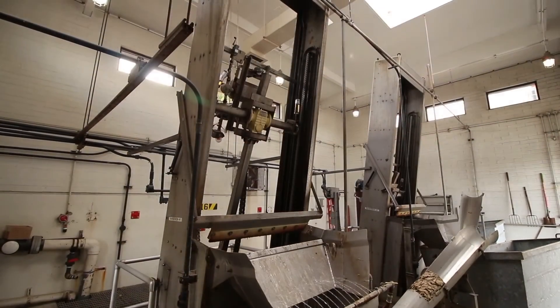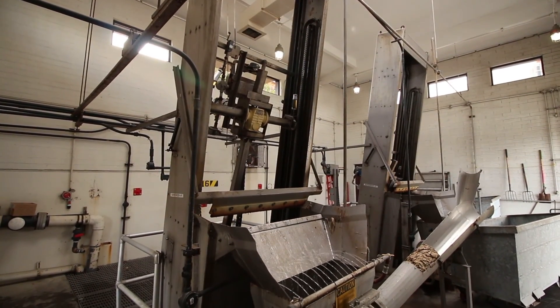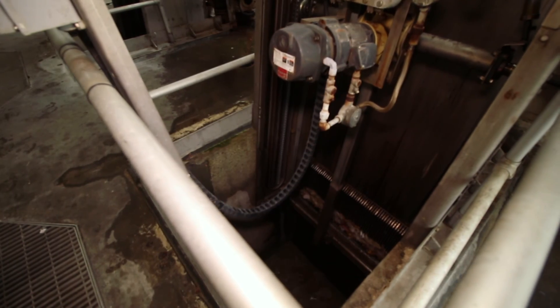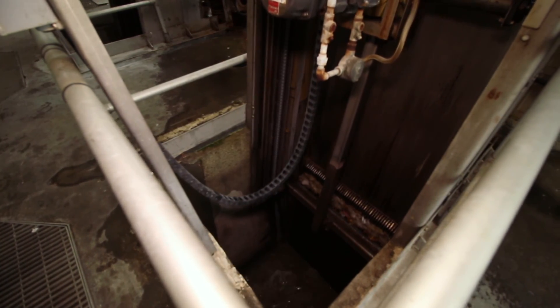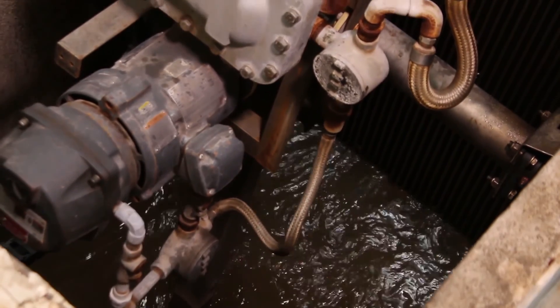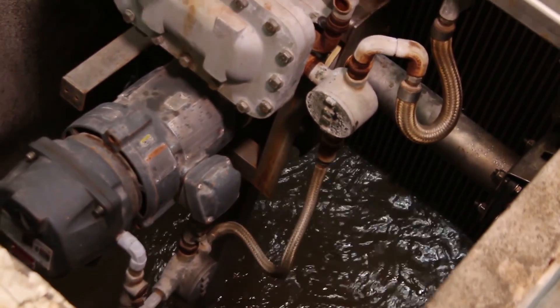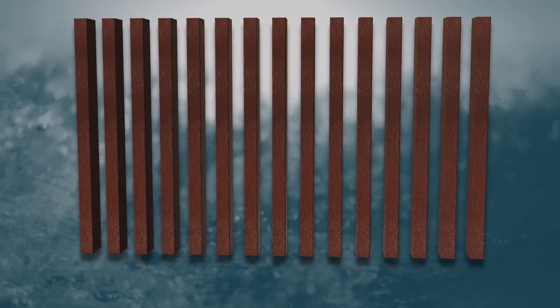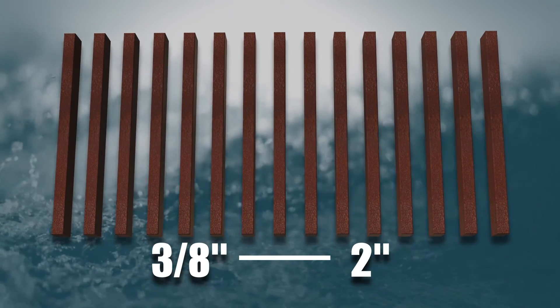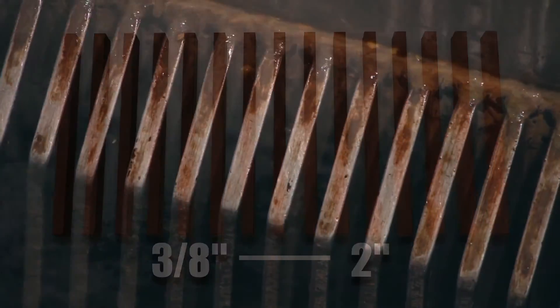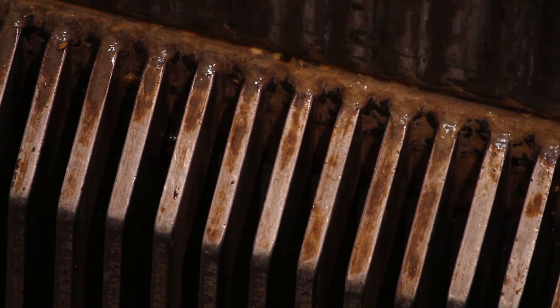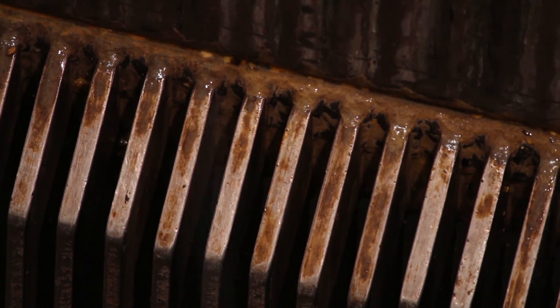This facility has two mechanical bar screens running in parallel. Each screen is mounted in a channel where wastewater or sewage flows through. The screen traps solid material such as rags or rocks. Bar screens are designed with evenly spaced parallel bars from three-eighths to two inches apart. This unit has a spacing of one-half inch between bars, so any item larger than one-half inch is trapped behind the bars.